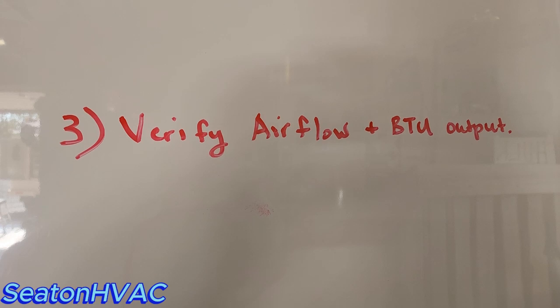Verify your airflow and your BTU output. This one's really easy to do on a gas furnace or even a heat pump. There's formulas, look them up, for how to convert your furnace temp rise or your electric furnace or heat pump temp rise to BTUs. Make sure it's giving the house the proper BTUs for the load. And obviously you're going to want to make sure that your temp rise is within specs on your gas furnace. It's on the rating plate of all of them.